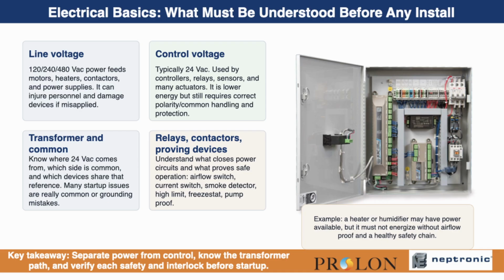Before installation or startup, everyone must clearly understand the electrical distinction between line voltage and control voltage. Line voltage powers motors, heaters, and other high-energy devices. Control voltage is what the controller and most field logic circuits use to sense and command operation. One of the most common causes of field damage is confusion between the two.